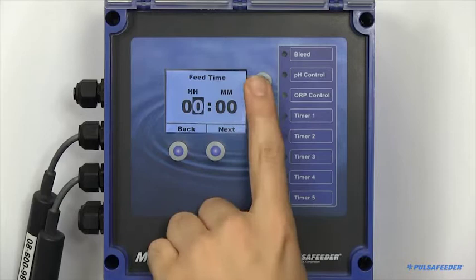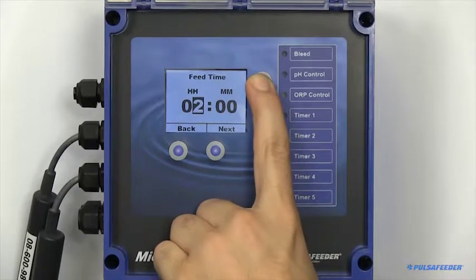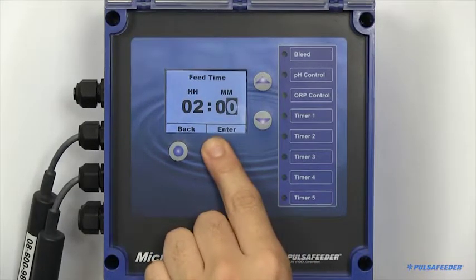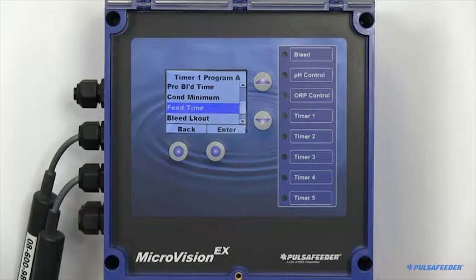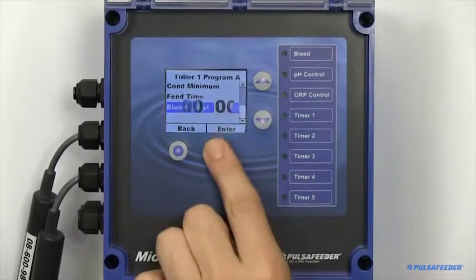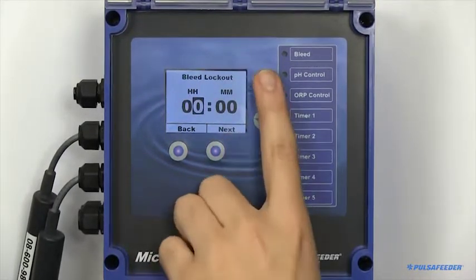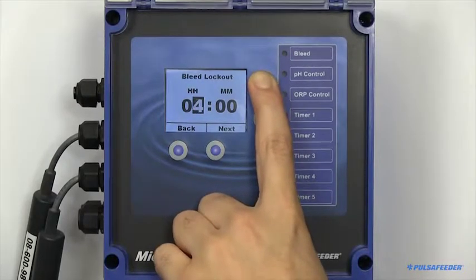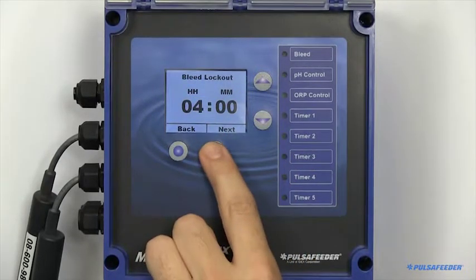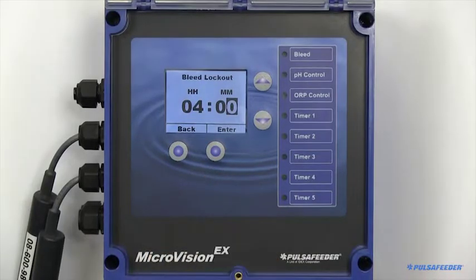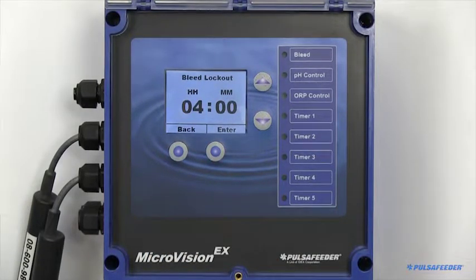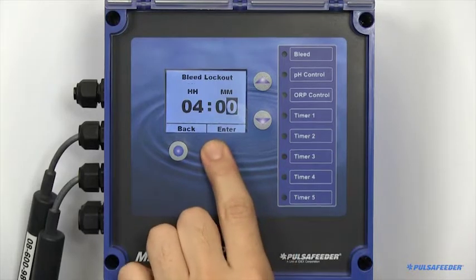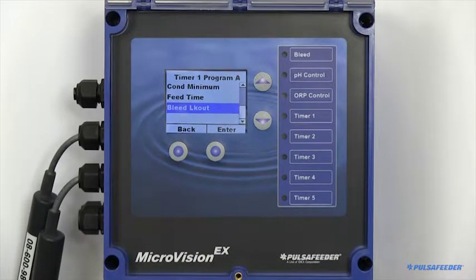Next, specify your feed time, or how long you would like to feed chemical. To prevent your tower from bleeding costly chemicals, you can also set a bleed lockout, or the amount of time you would like to prevent your tower from bleeding water from the system. Note that this timer begins when your feed cycle begins. For the lockout to last longer than your feed time, please specify it as such.